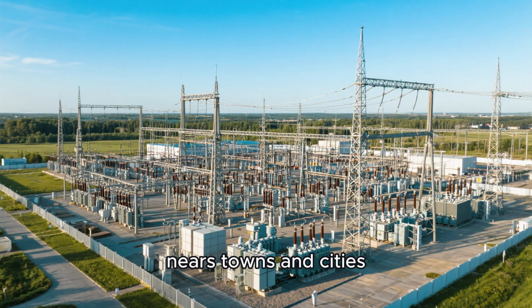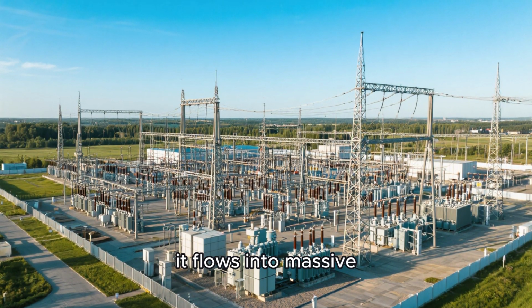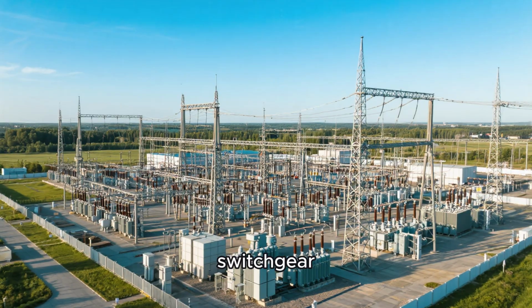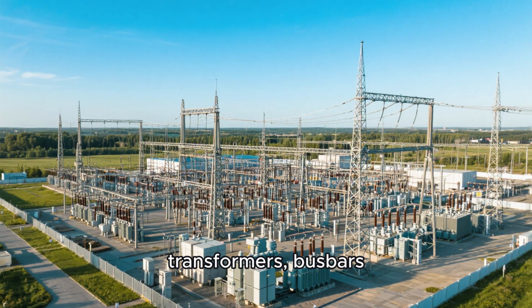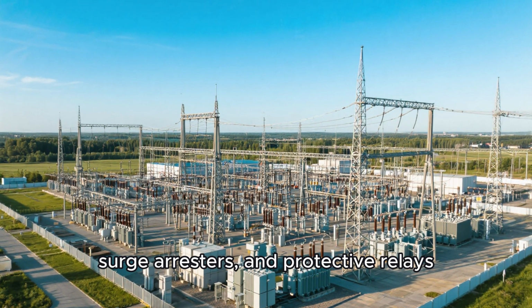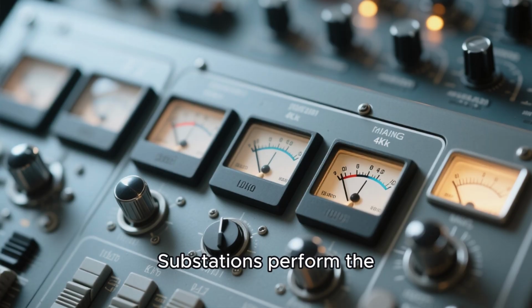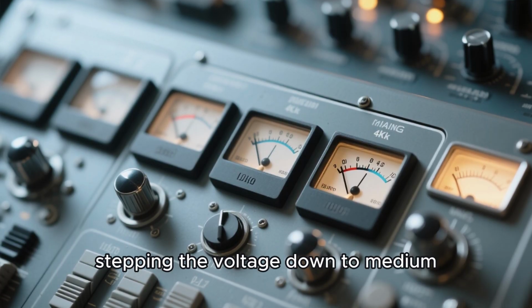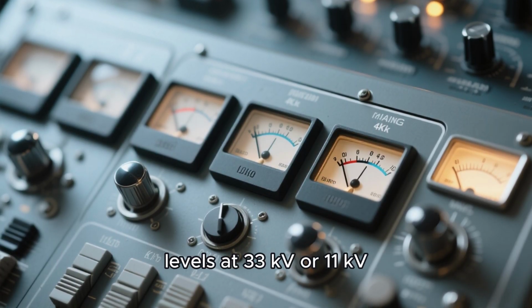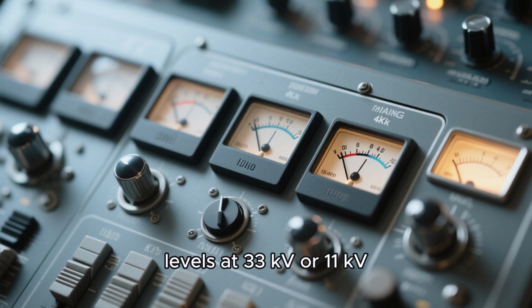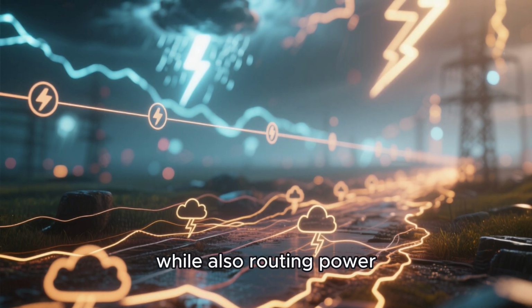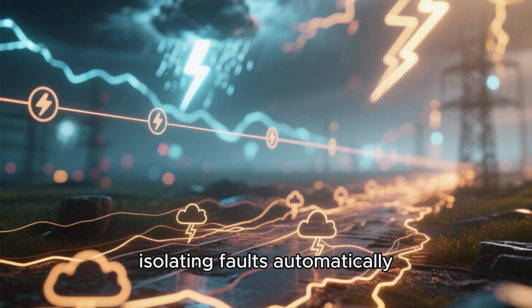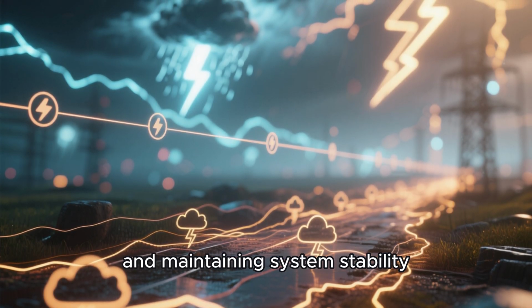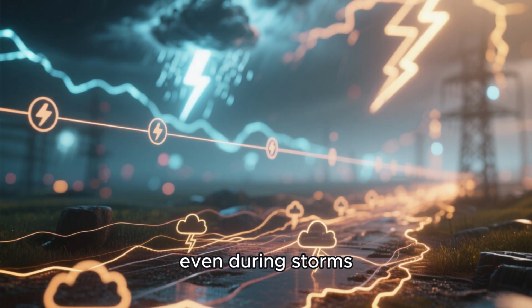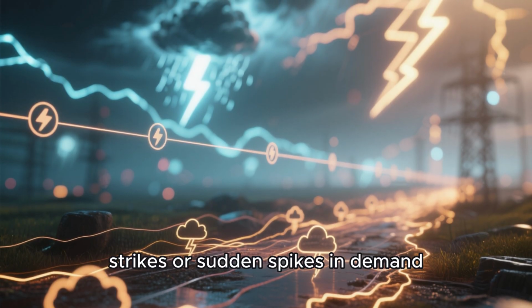As the electricity nears towns and cities, it flows into massive substations filled with switchgear, transformers, bus bars, surge arresters, and protective relays. Substations perform the critical job of stepping the voltage down to medium levels, 33 kV or 11 kV, while also routing power through multiple feeders, isolating faults automatically, and maintaining system stability even during storms, lightning strikes, or sudden spikes in demand.